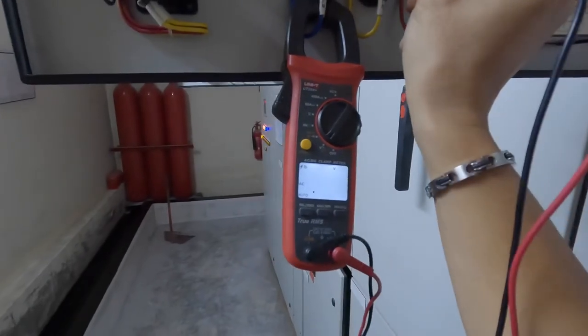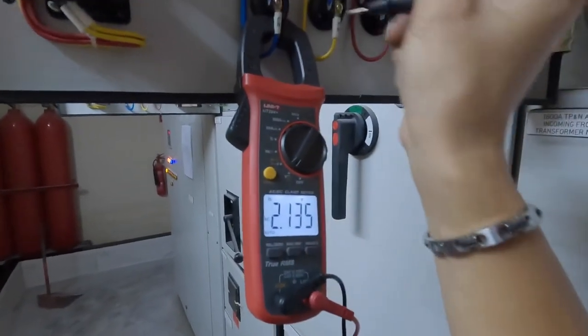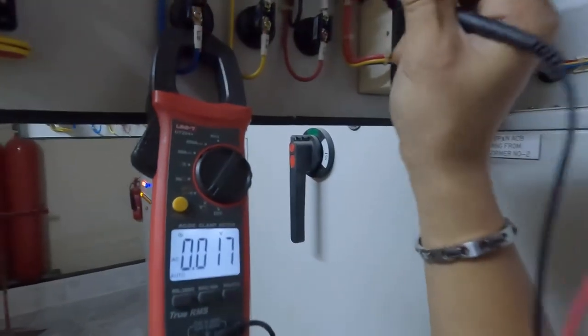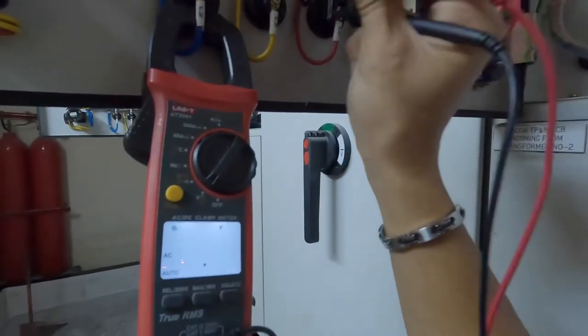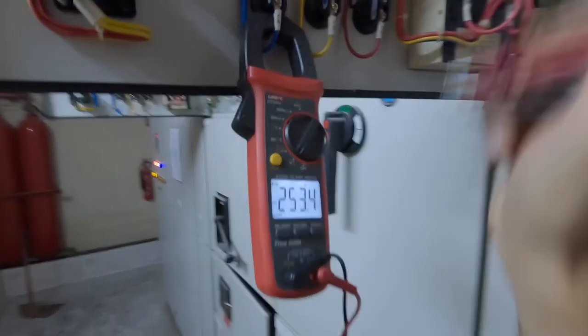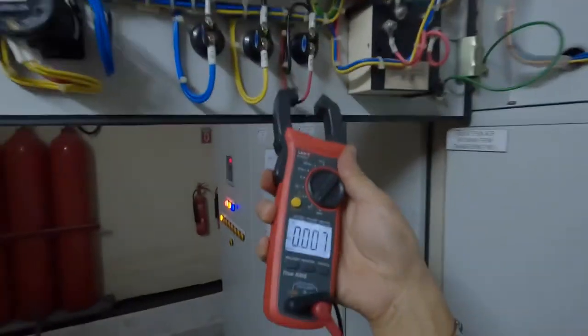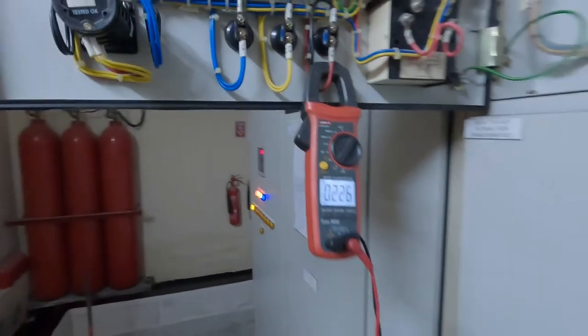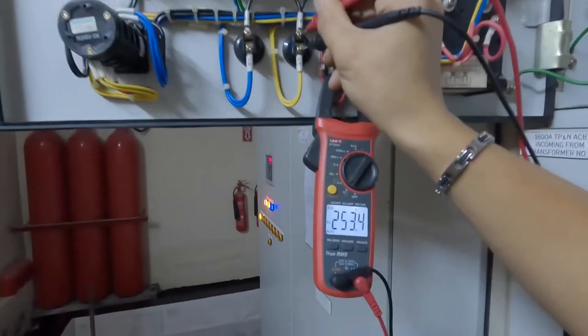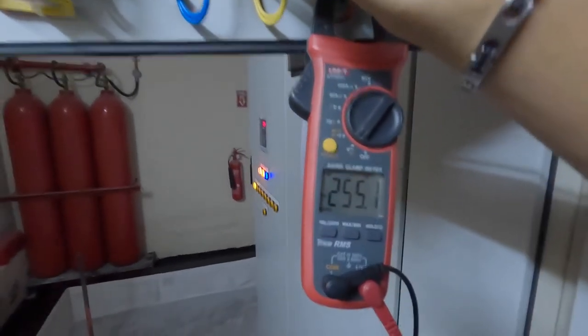The yellow phase reading — due to the indicator light fuse we don't get any reading. The voltage is 253.5V — quite high. Advise to change the transformer tap. This higher range of voltage fluctuation can easily cause damage to connected equipment. Yellow phase: 253V, blue phase: 255V — this is the highest. Not advisable.